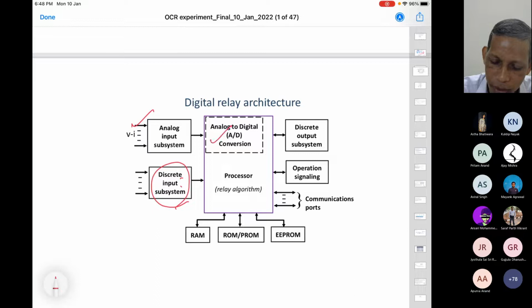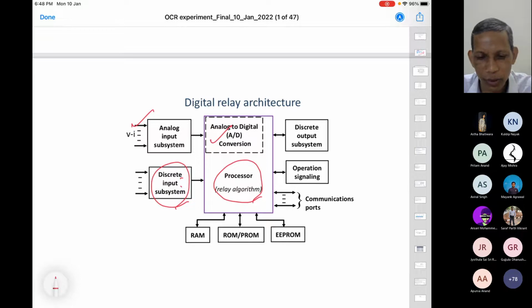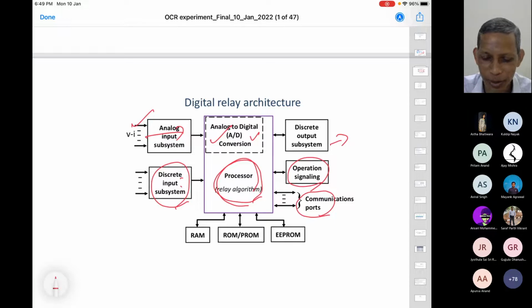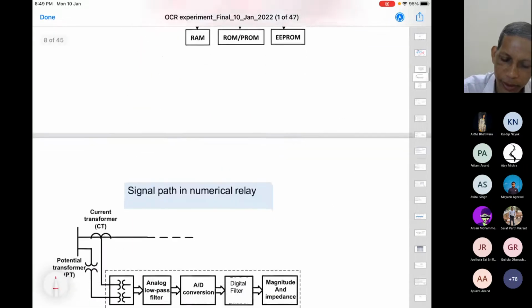It converts analog to digital, and then we have the processor, like my laptop. This processor takes the corresponding samples and uses them to find the required things, and then derives a trip command, trip or no trip, remain silent. So it can communicate to others, and it can operate the corresponding circuit breaker. This is as simple as that. The input analog signal is converted to a digital signal by the A to D converter, and then processed by the algorithm, the brain part, the important part of the relay, otherwise called the brain of the protection. You can say the protection system is nothing but the relay, and it derives the trip or no trip decision. It is as simple as that.